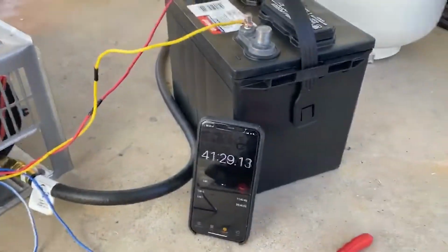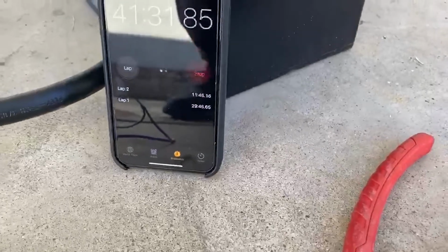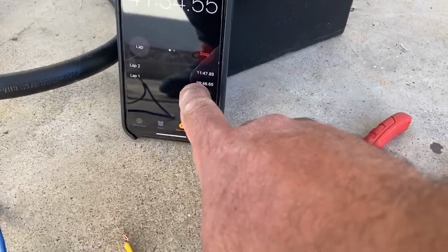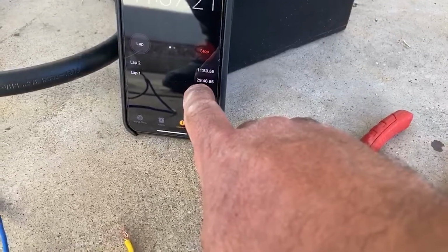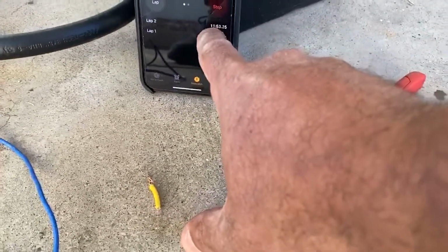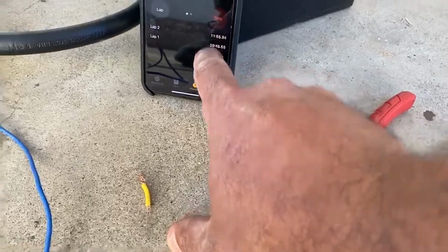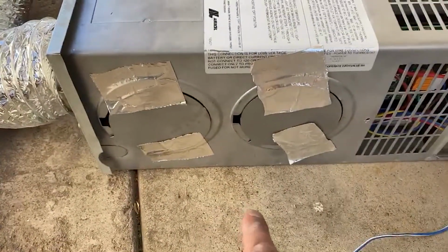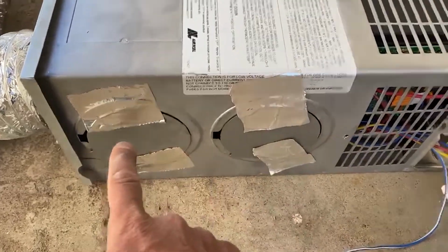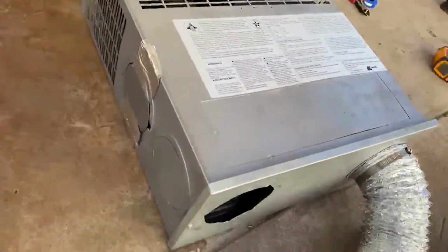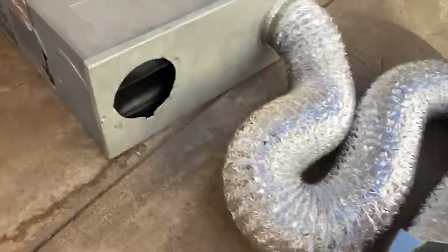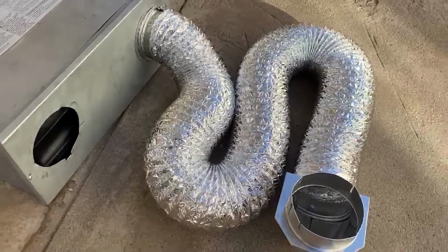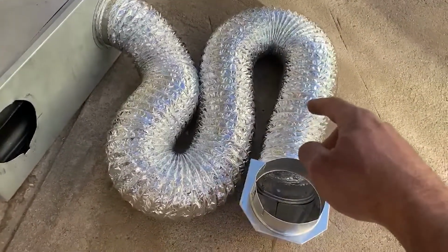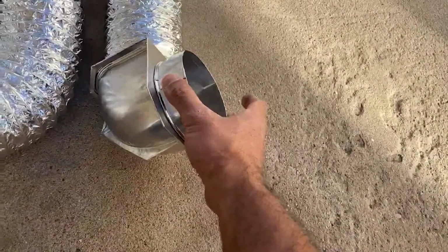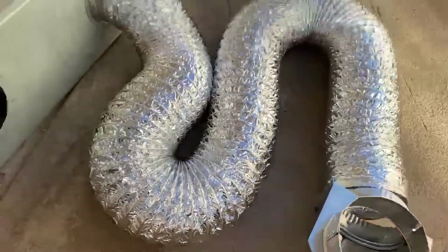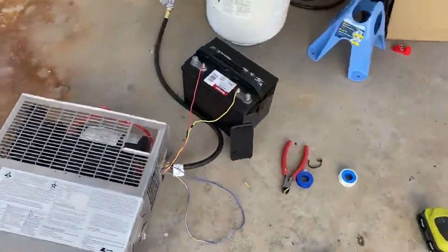The furnace doesn't turn off. I ran it for 29 minutes with 5 ducts open with no stop, and I ran it for another almost 12 minutes, restricting, purposely abusing the furnace, restricting 4 out of the 6, and then putting ductwork in that weird shape to create air restriction, plus a 90-degree, and I'm still running. The furnace doesn't stop.